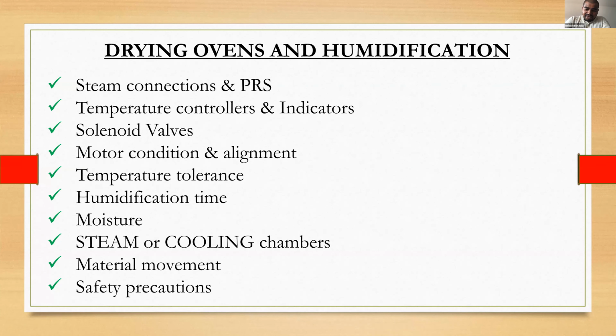So we have to maintain several things. Number one, steam connections: there should be no leakage, and it should be insulated. PRS, the pressure regulation system, is also most important, because from the boiler it comes at around 6 to 7 bar pressure. If that pressure goes directly to the solenoid valve, it just gets burned and cannot perform well. Once the solenoid burns, we cannot tell if it is burned or working - we can't know until we open and check, and most people will not open and check. I'm damn sure. So we have to put a pressure regulator.